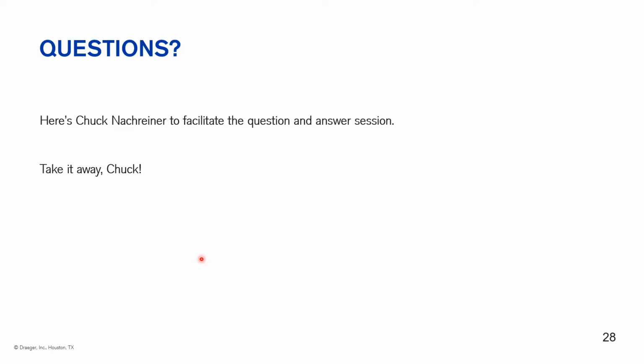Thanks, Russ. There were two other questions, but they concern the same thing. It's pretty much about calibrations and the difference between what is really required of your instrument, and will a bump test suffice? Well, depending on the type of bump test that's done, there's a quick bump test, which is just an exposure to gas to make sure it goes into alarm. Or there's an extended bump test, which is more of a calibration check, where we're looking at the target gas value within a plus or minus 10 to 20% tolerance. Typically, if you do an extended bump test and you fall within that tolerance, you're good to go. You really shouldn't need to recalibrate that instrument. If you're outside that tolerance, that's what would drive the need to recalibrate.